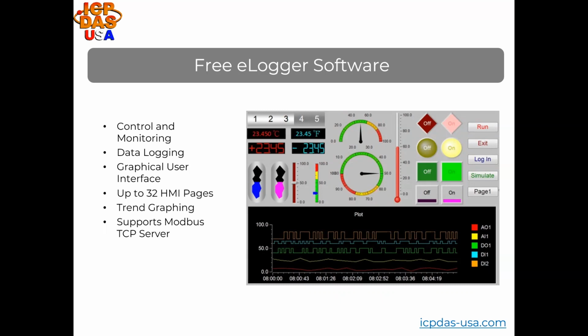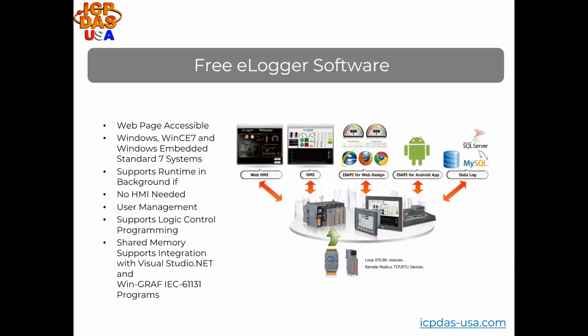eLogger supports Modbus TCP server, so you can read and write data with Modbus TCP protocol. You can publish eLogger to a web server, so it's web page accessible for remote monitoring and control. It runs on Windows, WinCE 7, and Windows Embedded Standard 7 systems. You can use it in the background, so if no HMI is needed, you can still use eLogger, for example, to make the data logs.